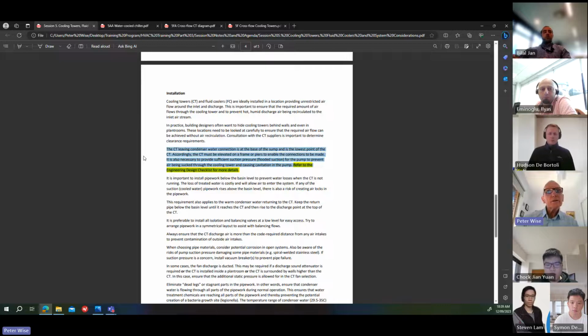The cooling tower leaving condenser water connection is at the base of the sump of the cooling tower and is the lowest point. Accordingly, the cooling tower must be elevated on a frame or piers to enable the connections to be made. It's also necessary to provide suction pressure, flooded suction, for the pump to prevent air being sucked through the cooling tower and causing cavitation in the pump.